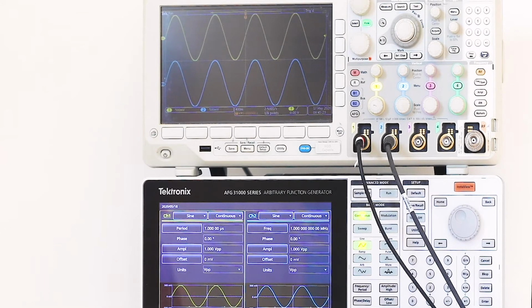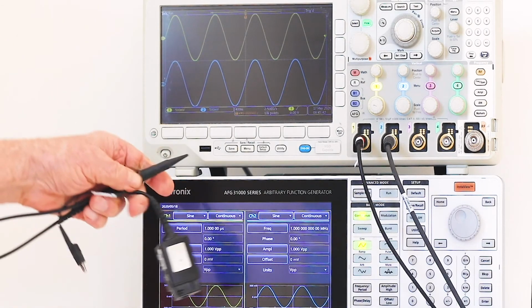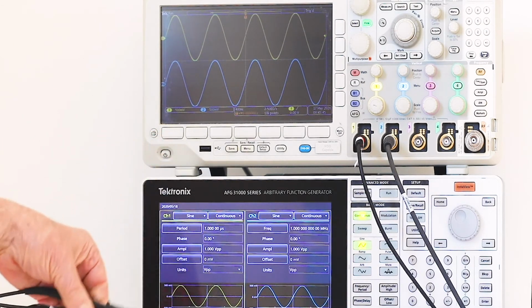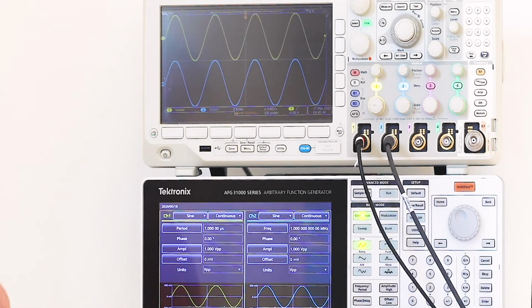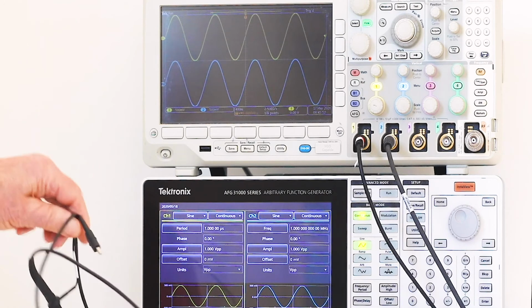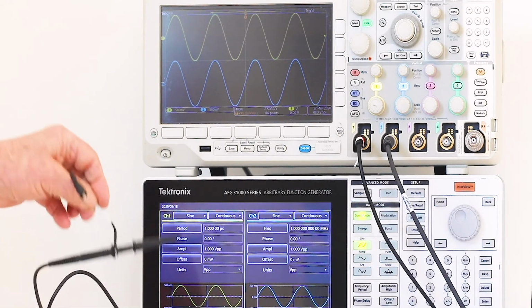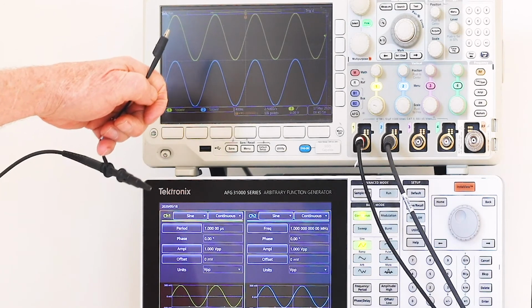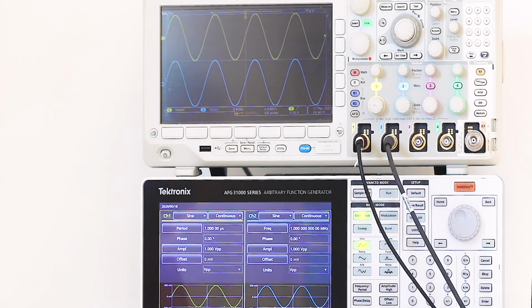It is to be emphasized that it doesn't matter whether the oscilloscope is powered on. As long as it is plugged into the receptacle, this potential hazard exists. There is no problem in connecting the probe tip to this floating voltage. Here's the probe tip. And this is the ground return lead. The hazard arises from the ground return lead connection.